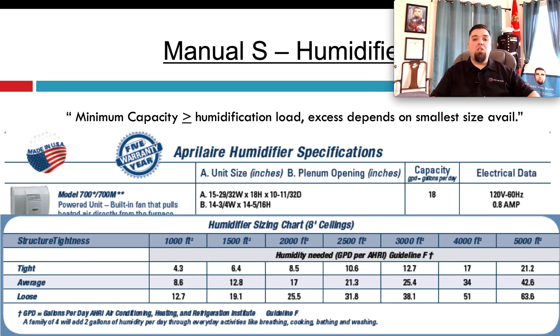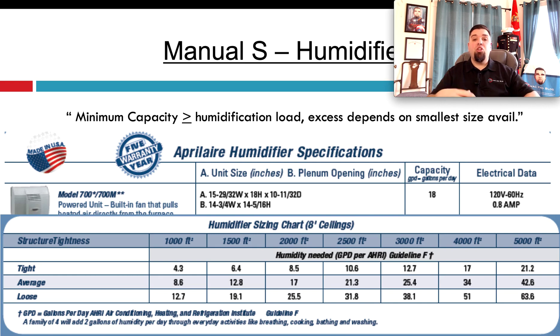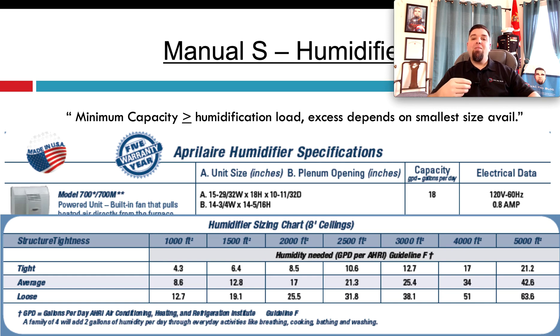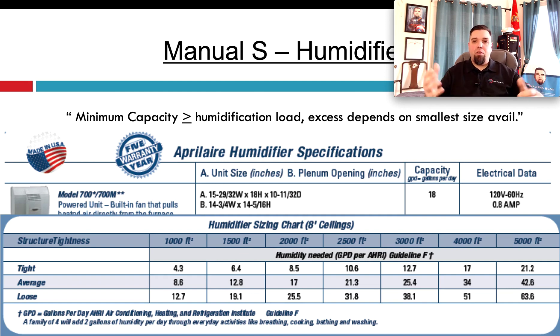In that example, we have 21.3 gallons per day needed. Keep in mind that's the total need. A family of four will add two gallons of humidity per day just through normal activity — cooking, bathing, washing, and breathing. So we subtract that two gallons from the 21.3, and we need about 19 gallons a day. I would recommend we go to the next size up for humidifier specs.